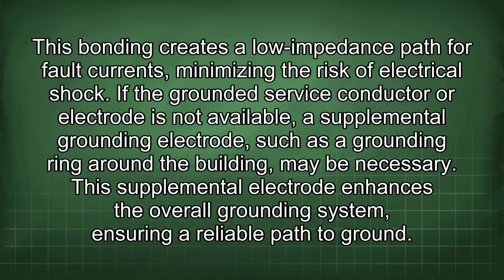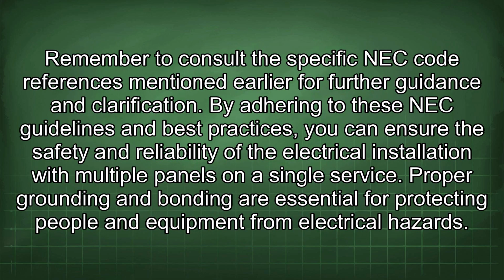If the grounded service conductor or electrode is not available, a supplemental grounding electrode, such as a grounding ring around the building, may be necessary. This supplemental electrode enhances the overall grounding system, ensuring a reliable path to ground. Remember to consult the specific NEC code references mentioned earlier for further guidance and clarification.